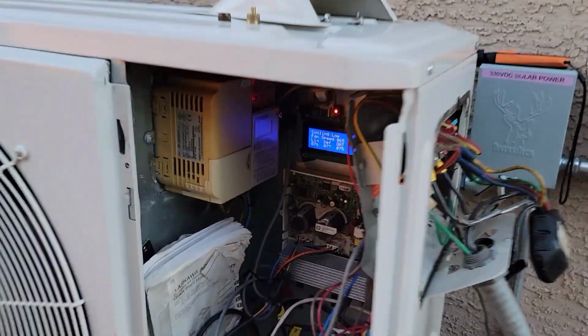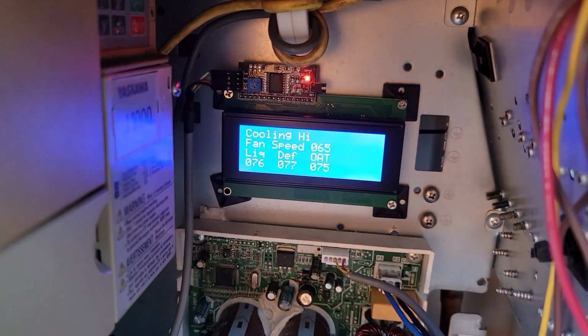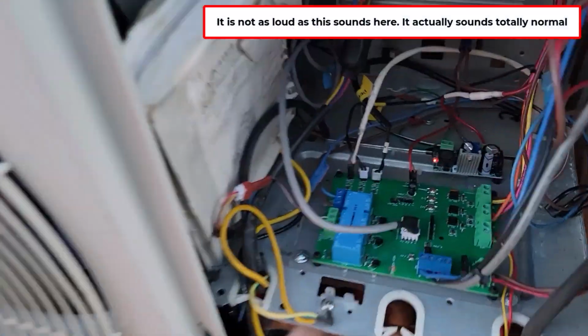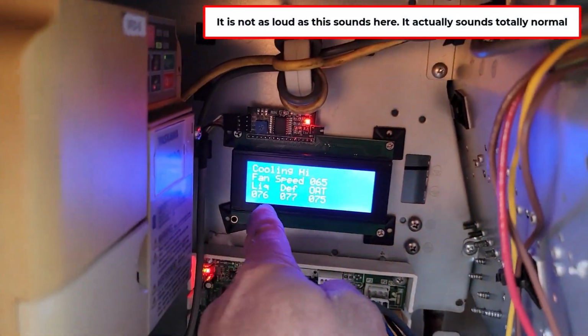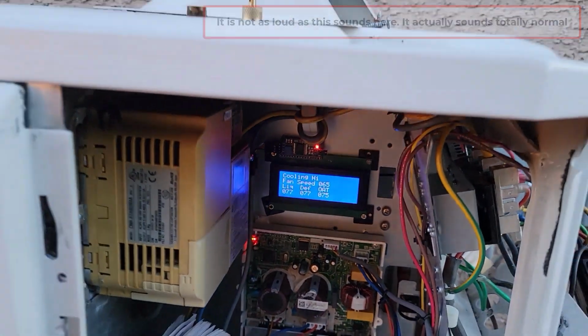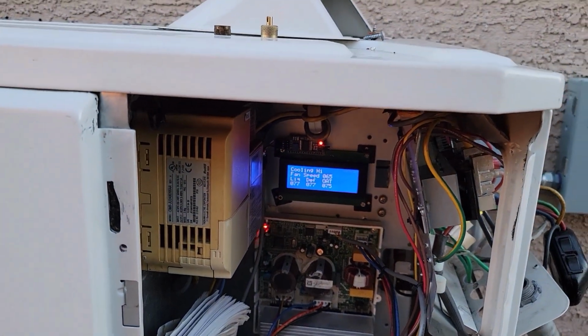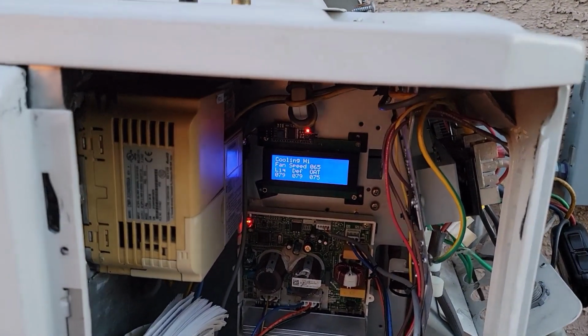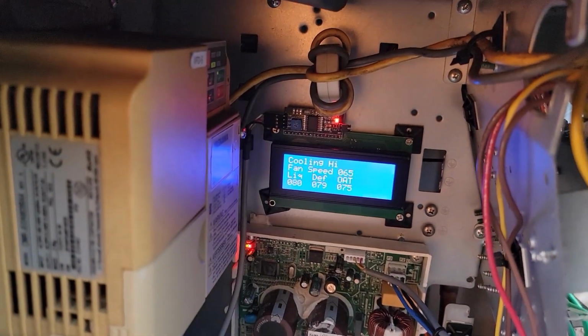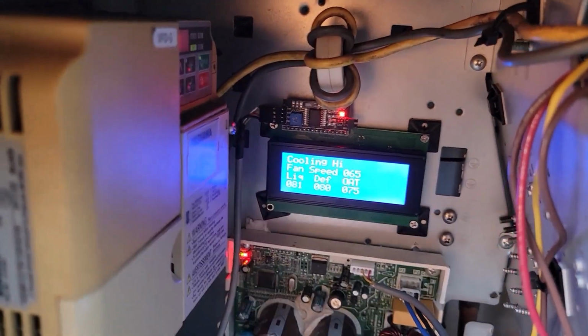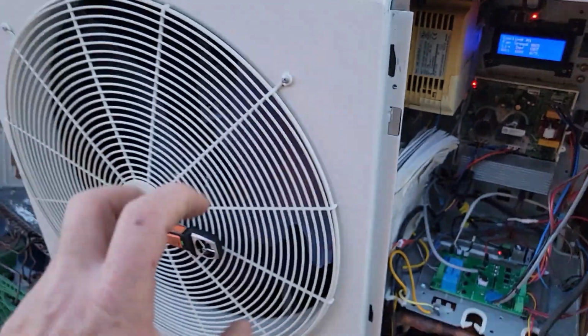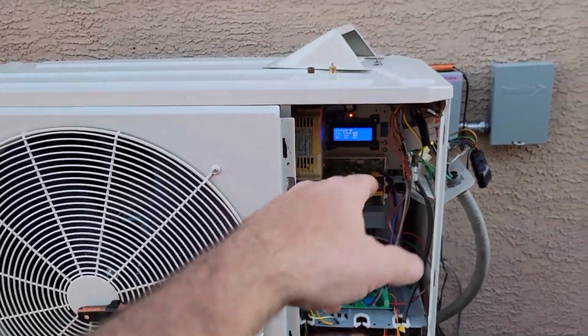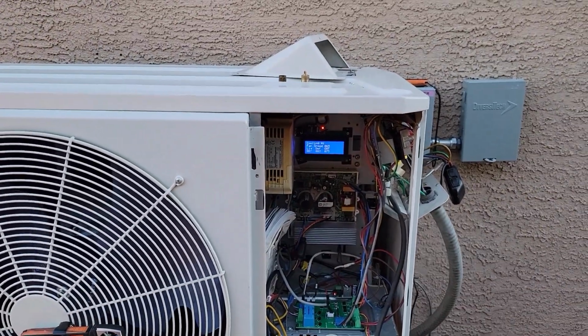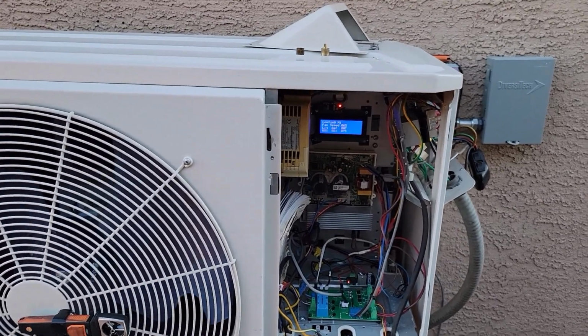And there she already goes. It switched, went on, and then I went to cooling high. Fans are not running because I have a thermistor plugged in. So liquid line 76, and I think a little 87 or somewhere, and I forget where I set it for, but it's going to start kicking on the fans and speeding up. Fan speed says 65. That's because that's the minimum pulse width modulation I programmed in. That's an 8-bit value, 0 to 255, so 65.